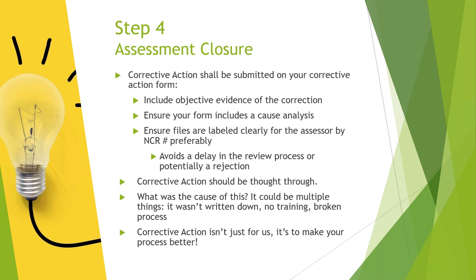The corrective action should be submitted on your own form — in 17025 or any ISO standard we accredit you to, you're required to have a corrective action process, so use your own form. Supply your corrective action response on your own form, make sure you have a root cause — what led to the problem. Ensure your files are labeled clearly for the assessor: if you have five NCRs, label folders NCR 1, 2, 3, 4, 5. Provide your objective evidence to support the corrective action. Assessors like to see that you took time to do a good root cause and took corrective action to ensure the issue doesn't recur. Corrective action isn't just to appease us — it's to make your process better.